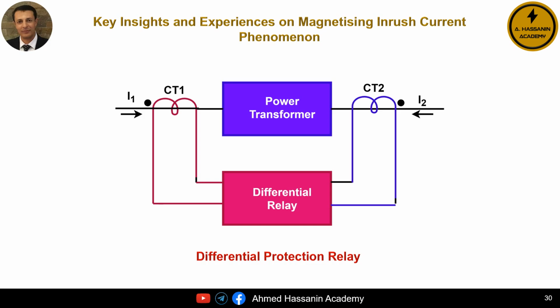It's important to note that the differential protection relay may cause an incorrect trip of the transformer, as the trip is triggered by the magnetizing inrush current and not by a fault or short circuit inside the transformer. As we mentioned earlier, the phenomenon of magnetizing inrush current is considered a normal, transient phenomenon within transformers, which vanishes within a very short period, typically not exceeding 1 second or slightly more.